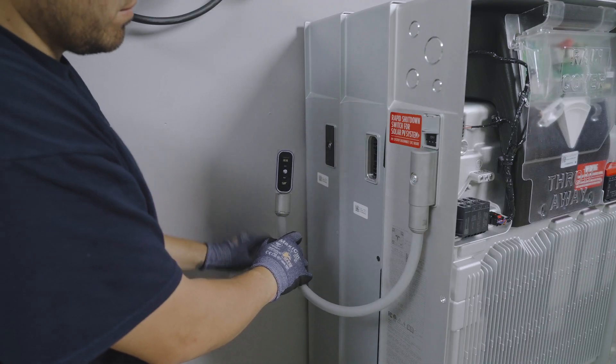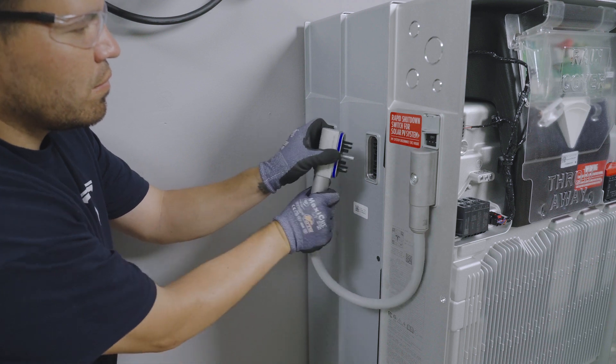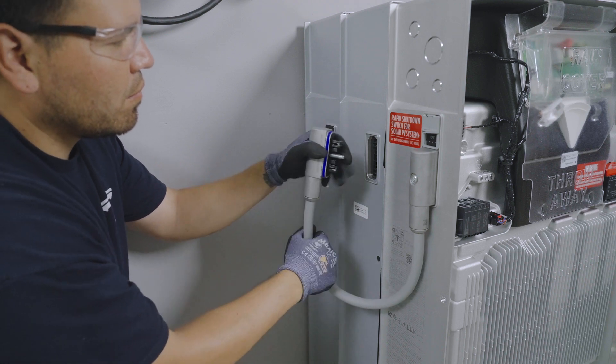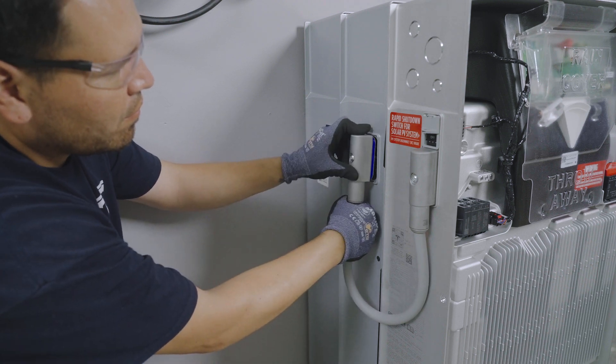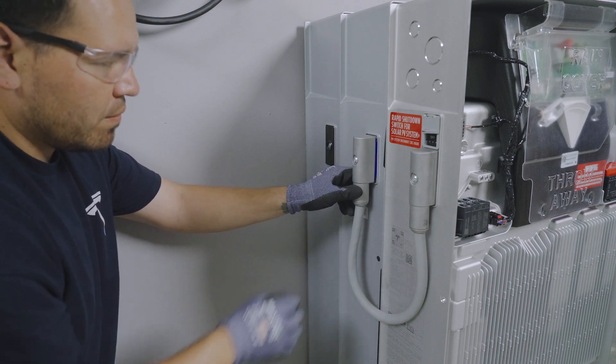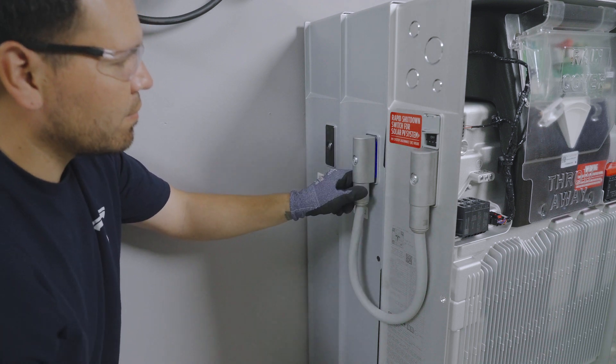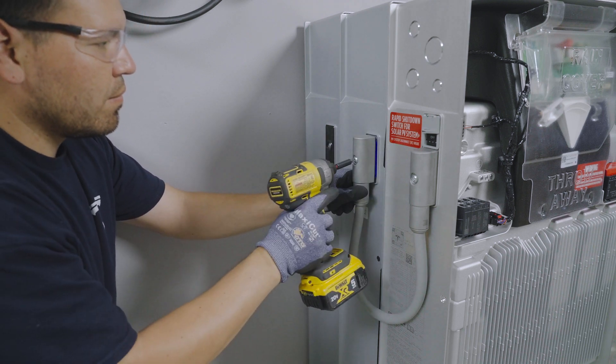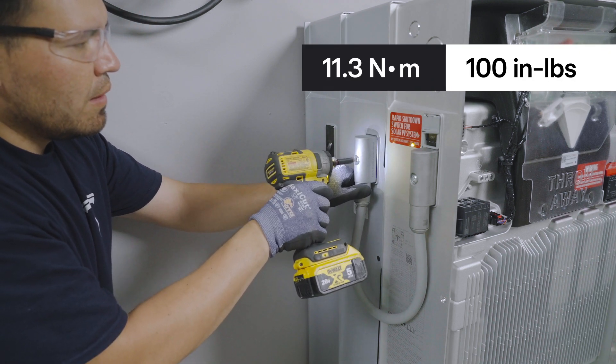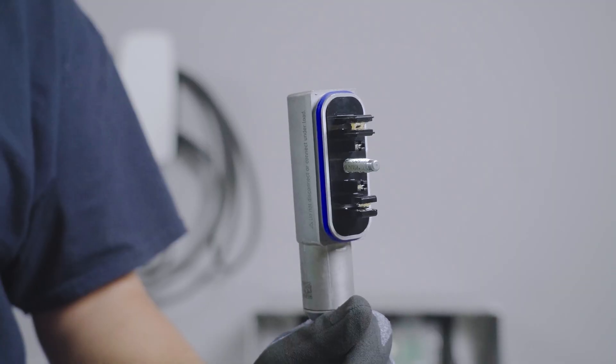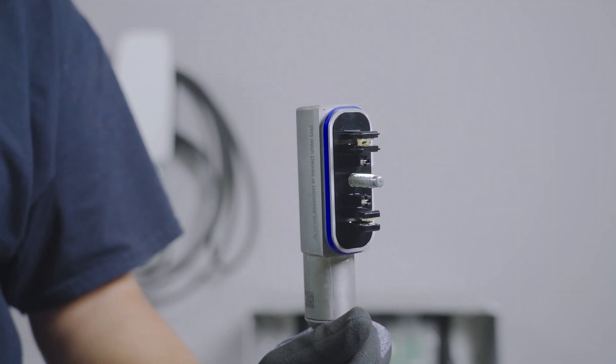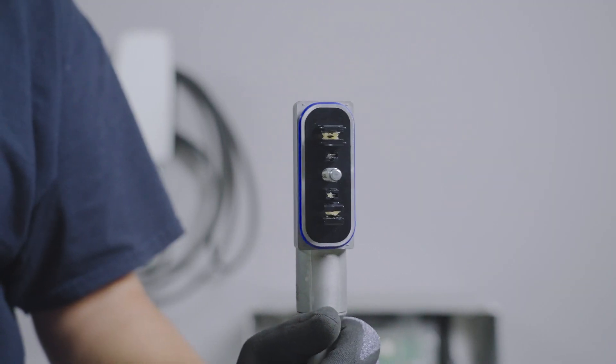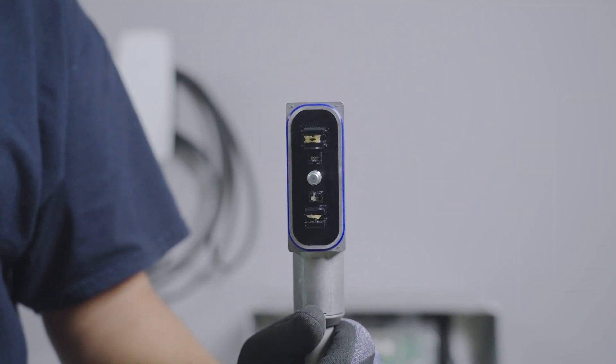Route the other end of the wiring harness to the next unit, either another expansion or Powerwall 3. Connect the other end of the wiring harness to the next unit and secure with a T40 screw, tightening to the specified torque value. If a wiring harness is dropped or otherwise damaged, dispose of it and use a new harness.